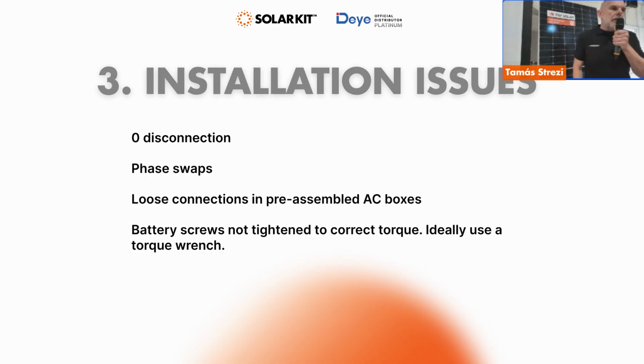And whenever I go out for a repair, I always do routinely, I tighten the bolts on both sides of the terminal, because the Chinese manufacturers sometimes do not tighten these enough, and there were some loose connections, not on the user side, but on the inverter side. So as a routine, I go through them, and let's say 1 in 10, I find some connections which are not tight enough. Also, the pre-made junction boxes, AC and also DC junction boxes, always make sure that the connections are tight and secure. And the most important place where secure connection needs to be established is the battery side, because the amperage is much higher.